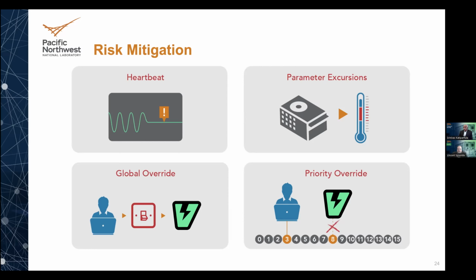We also provide global overrides and local overrides, shown at the bottom. A global override means if the building operator decides not to participate, they can override themselves. At the device level, each individual device can also do the same thing through a priority override, which is a BACnet concept.